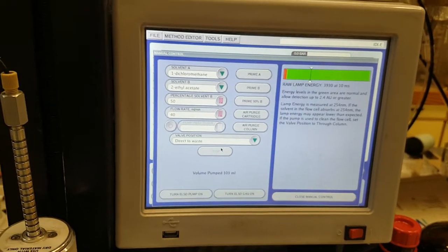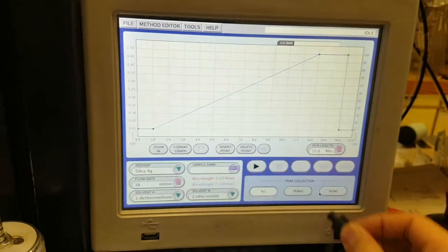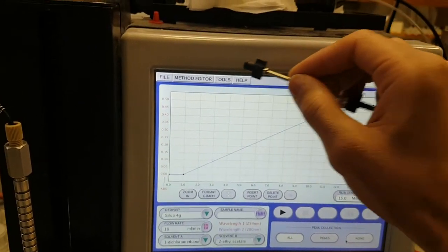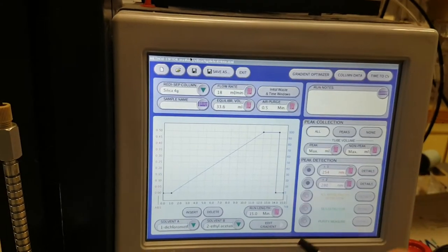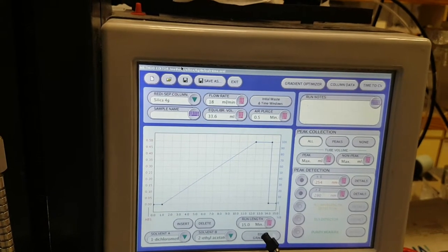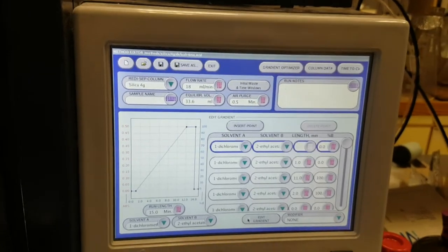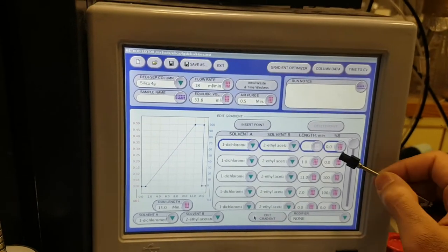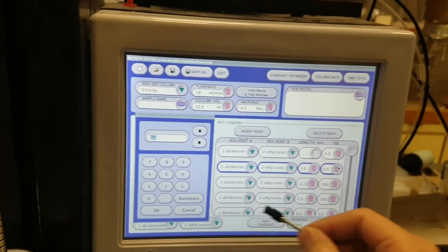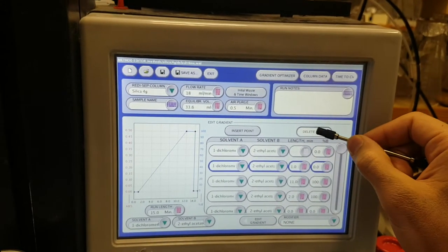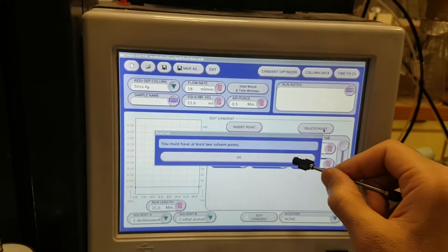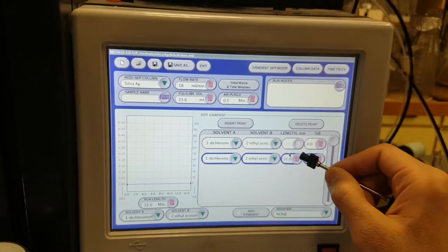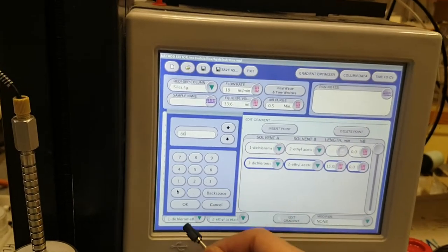The next step will be closing manual control. We will go to method editor then I'll try to choose my elution system. It is gradient. I will delete all of these points and I'll try to make 60 minutes.